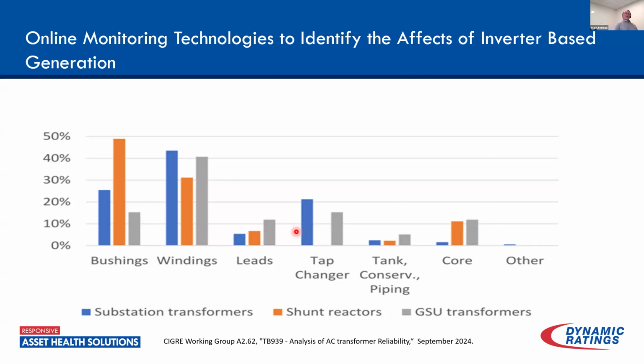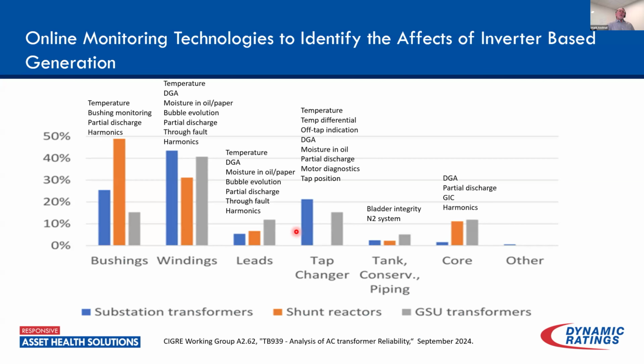So what do we do about all this? If you go back to the initial failure modes that we have and the components that are failing on our transformers, we can start to apply the monitoring technologies that can be used to help protect those assets. If we're talking bushings, we can monitor the temperature of the bushings, infrared and things like that, to make sure that we're not overheating. We can do bushing monitoring. Online bushing monitoring is a very, very effective technology to help identify degraded bushings. It works on pretty much any bushing type, whether it's the newer RIP and RIS bushings or the older OIP or the resin bonded paper.